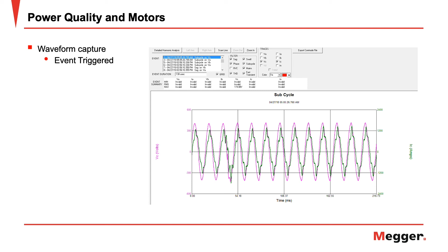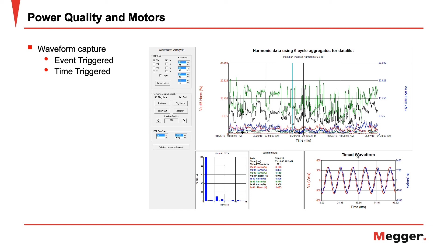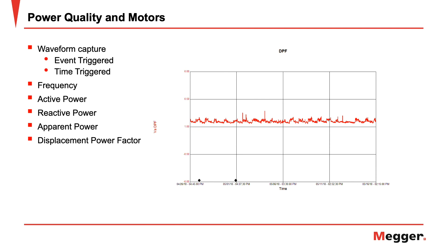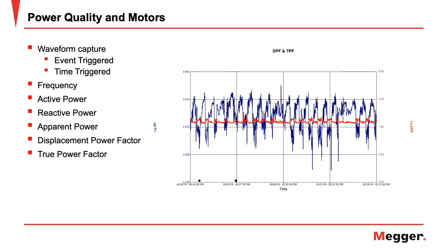The MPQ analyzer will also capture waveforms. Now, these waveforms can be triggered by events. The waveforms can also be triggered by time, and this can be done at the same time, so you can capture both time-triggered periodic waveforms as well as event-triggered waveforms. The MPQ will also trend frequency, active power, reactive power, apparent power, displacement power factor, which is the power factor of the fundamental without the harmonics, as well as true power factor, which is the power factor including the harmonics.